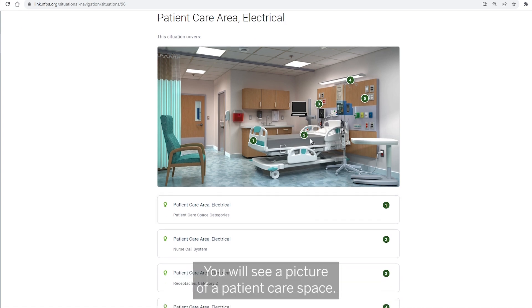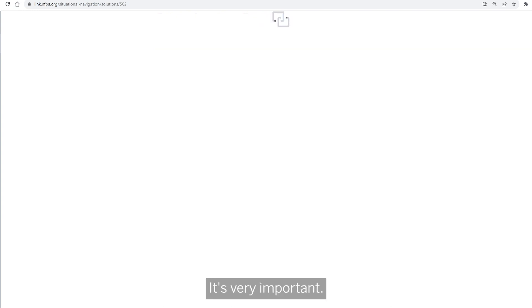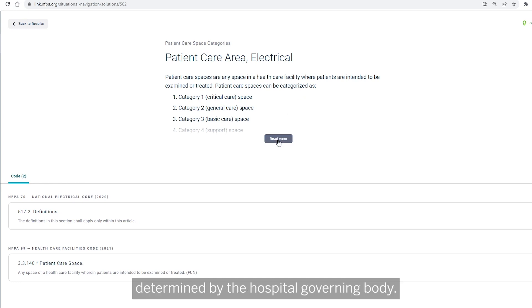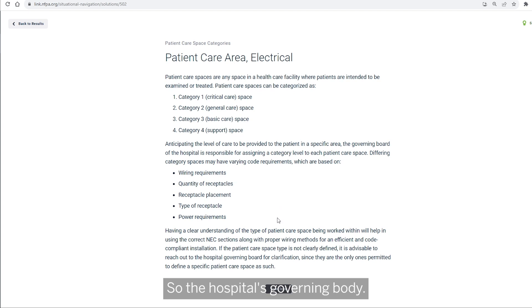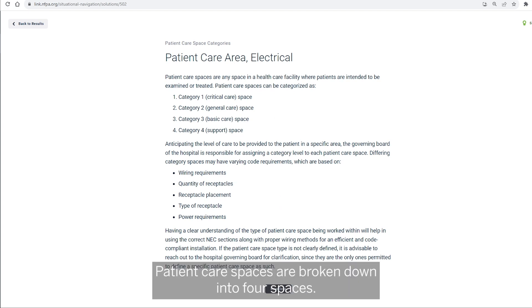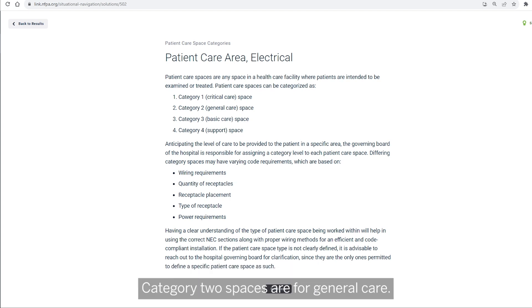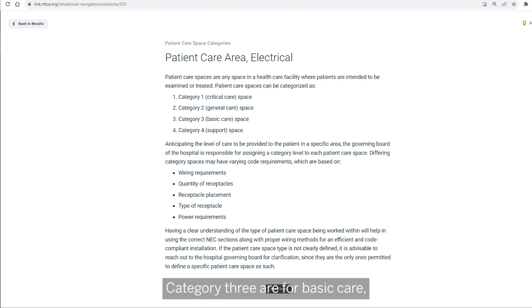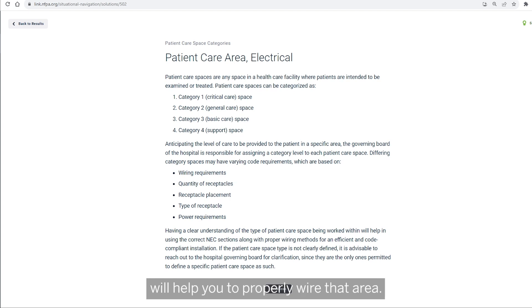You will see a picture of a patient care space. The first thing we're going to talk about is the categories — that's very important. Patient category spaces are determined by the hospital governing body. Patient care spaces are broken down into four categories: category one for critical care such as operating rooms, category two for general care, category three for basic care, and category four for support areas. Knowing what category space you are in will help you to properly wire that area.